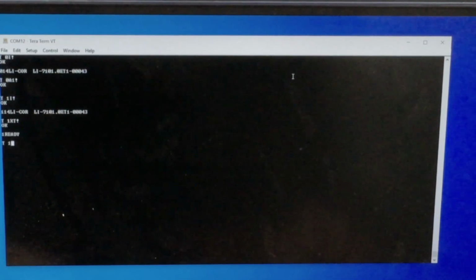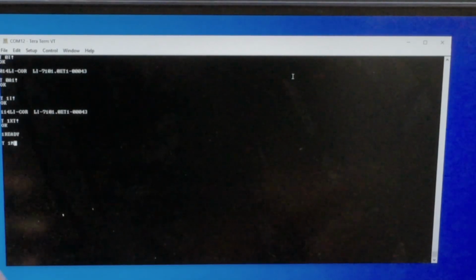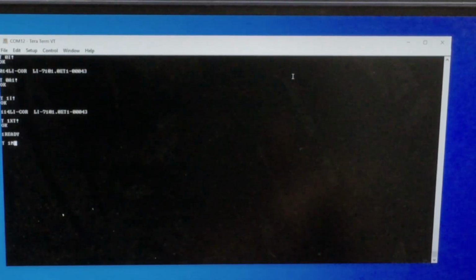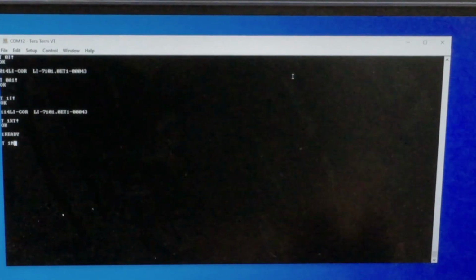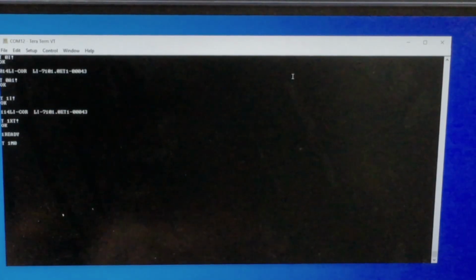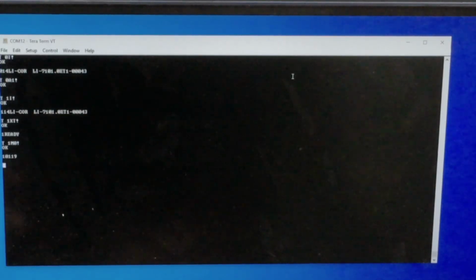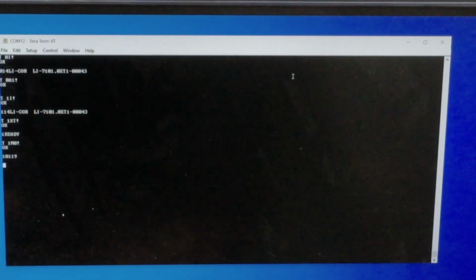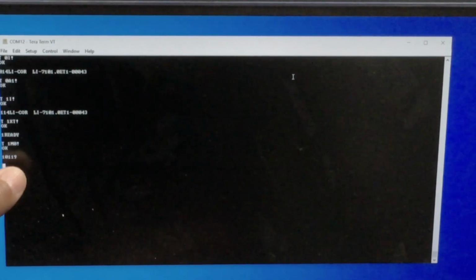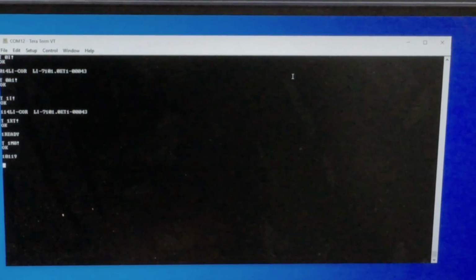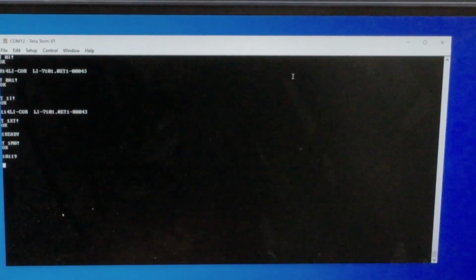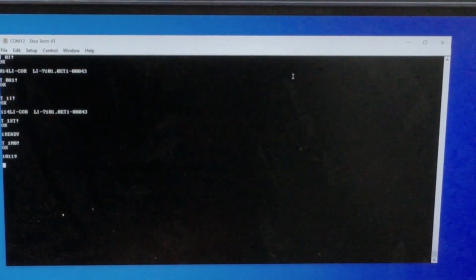To make a measurement, I again do the T, next the address which is the 1, and then the M. The M command can be M0, M1, M2, M3 - they all give different outputs, which are all explained in the manual. So for M0, I do the 0 followed by the exclamation. The sensor should respond with 10119, which tells me it has 9 outputs, and it's going to take 11 seconds to process that information and give you the fluxes.